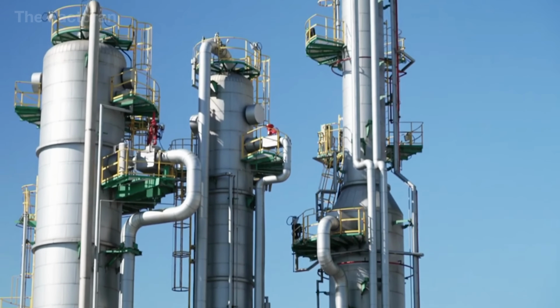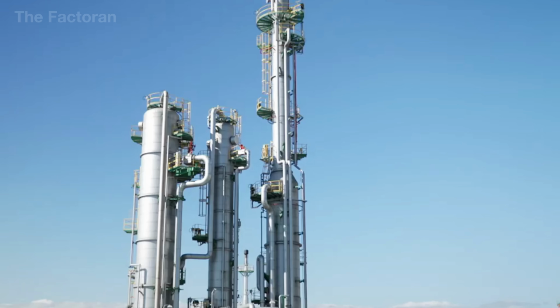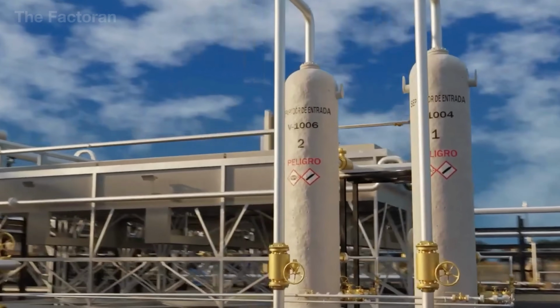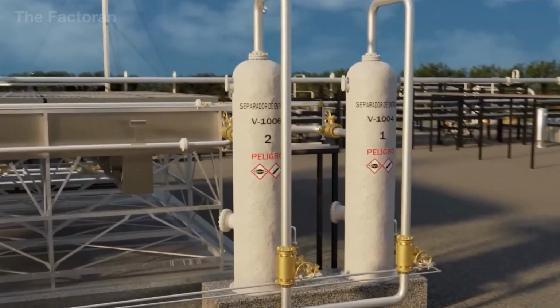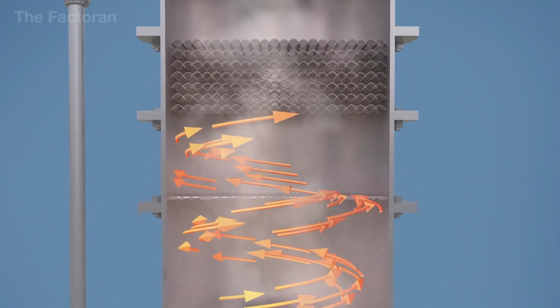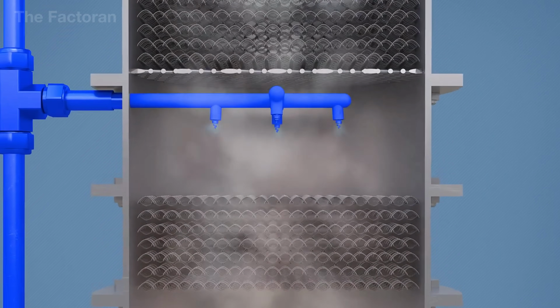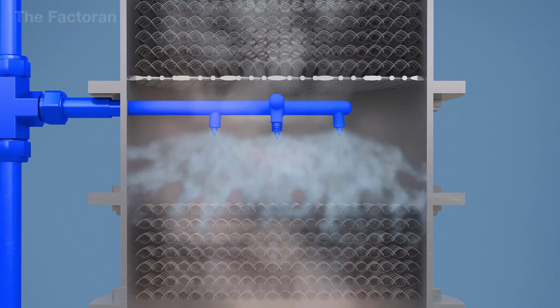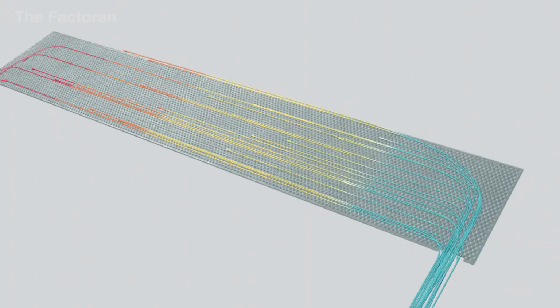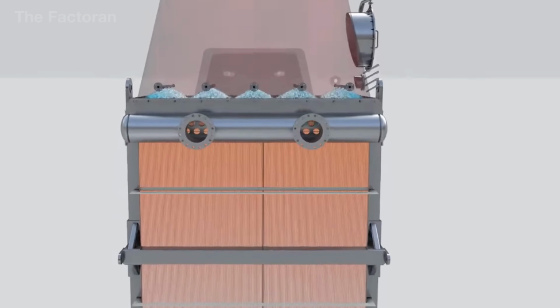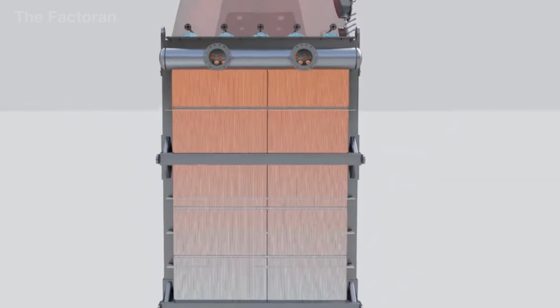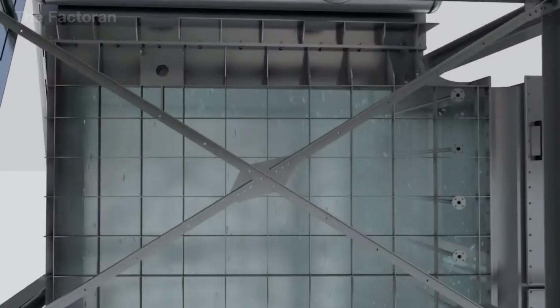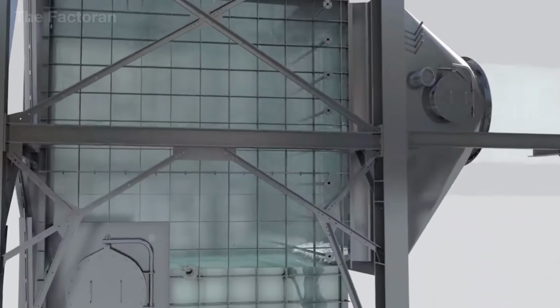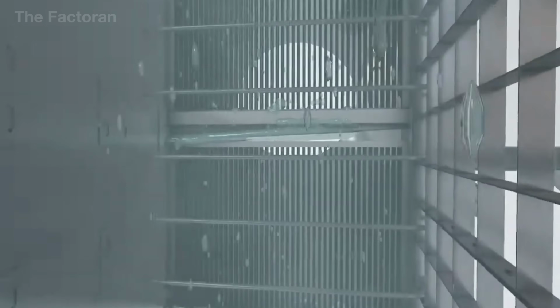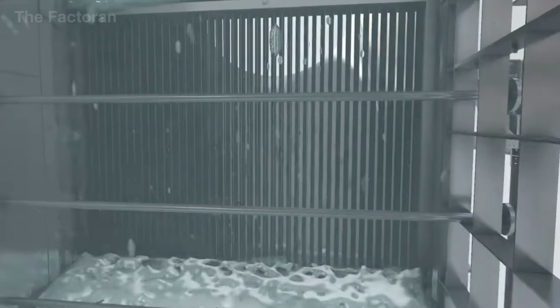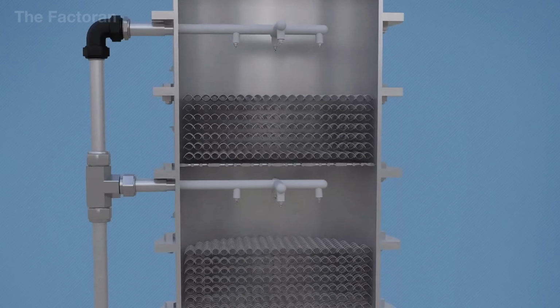Beyond reducing temperature, this stage also helps condense water vapor and remove part of the fine dust from the exhaust stream. Precise temperature control is critical. If it's too high, fabric filters and catalytic membranes downstream may be damaged. If it's too low, condensation can cause corrosion and clogging in the ducts. With automated control systems, temperature and coolant flow sensors are continuously monitored to ensure the gas leaving the cooling unit remains within safe limits before moving on to subsequent processes such as dust filtration, SO2 scrubbing, and NOx reduction.